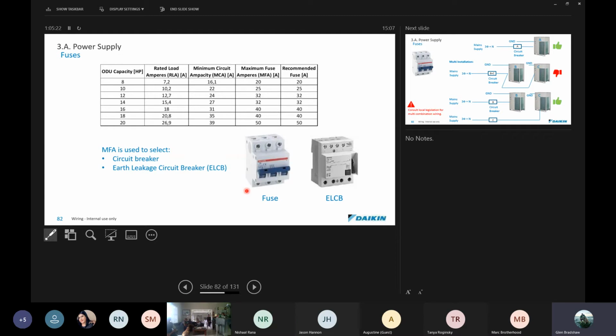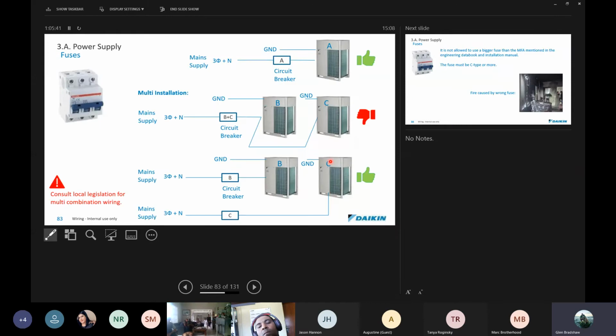So circuit breaker, this is something that you guys should all be familiar with. That is selected from the maximum fuse amperage, and the maximum fuse amperage is also used to select an earth leakage breaker if one is to be installed. Power supplies, you must consult your local legislation, especially with multi-combination wiring.